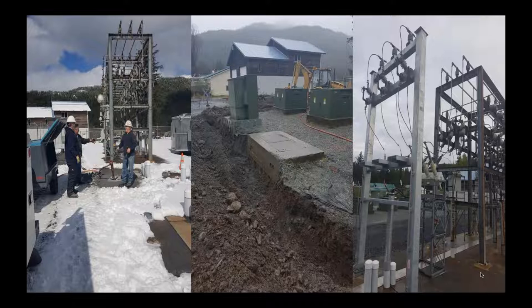Installing a new ground loop in the middle, extending our grounding grid. We tested our grounding and wanted to make sure we had a really solid ground plane. We also had to add a recloser in another section of bus in the substation.